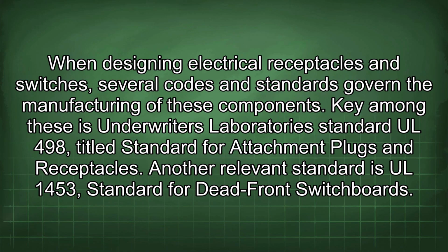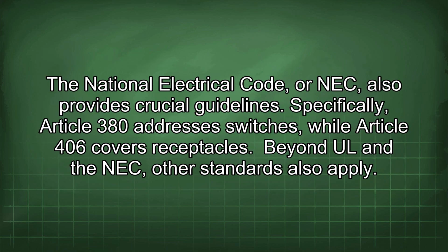When designing electrical receptacles and switches, several codes and standards govern the manufacturing of these components. Key among these is Underwriters Laboratories Standard UL 498, titled Standard for Attachment Plugs and Receptacles. Another relevant standard is UL 1453, Standard for Dead Front Switchboards. The National Electrical Code, or NEC, also provides crucial guidelines. Specifically, Article 380 addresses switches, while Article 406 covers receptacles.